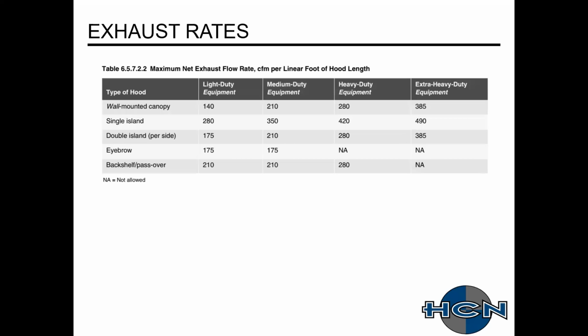And exhaust rates, this is actually from ASHRAE standard 154. They actually only require listed hoods now, but this used to be in that publication, I think prior to 2011. But also ASHRAE 90.1 has something similar, and 189.1. Typically, for 90.1, anything over 5,000 CFM, you have to abide by 3 requirements.